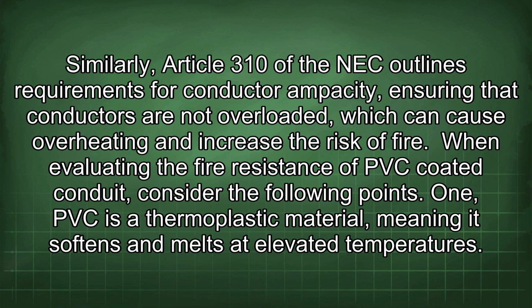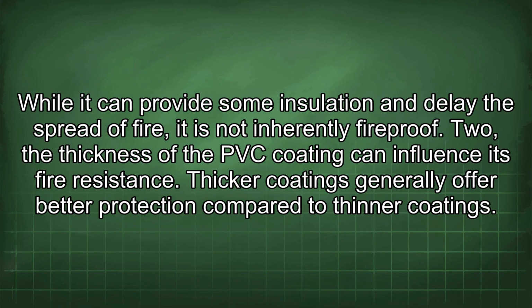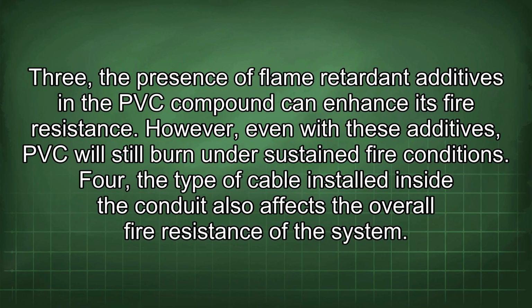When evaluating the fire resistance of PVC-coated conduit, consider the following points. 1. PVC is a thermoplastic material, meaning it softens and melts at elevated temperatures. While it can provide some insulation and delay the spread of fire, it is not inherently fireproof. 2. The thickness of the PVC coating can influence its fire resistance. Thicker coatings generally offer better protection compared to thinner coatings. 3. The presence of flame retardant additives in the PVC compound can enhance its fire resistance. However, even with these additives, PVC will still burn under sustained fire conditions.